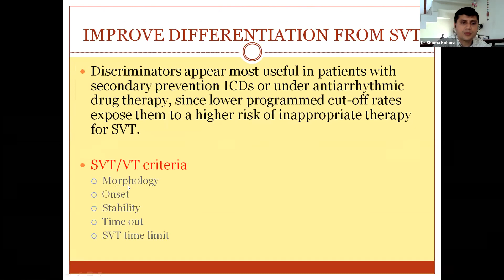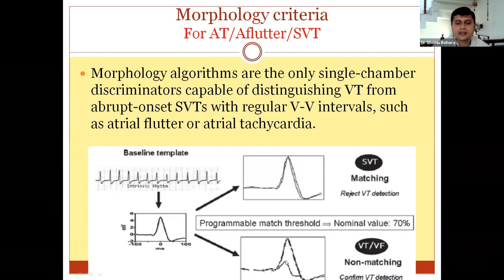The first and most important is morphology. Second is onset, stability, timeout, and SVT limit. A word about morphology. What the device does is collect a template in its database saying that this is my normal sinus rhythm, the intrinsic rhythm. And whenever the tachycardia occurs, it overlaps this template over the patient's own sinus rhythm template. If it matches more than a value of 70%, which can be programmed, it suggests that it's likely to be the same morphology and it's an SVT. But if it doesn't match and the match is less than the programmed value of 70%, then it says it's a VT.